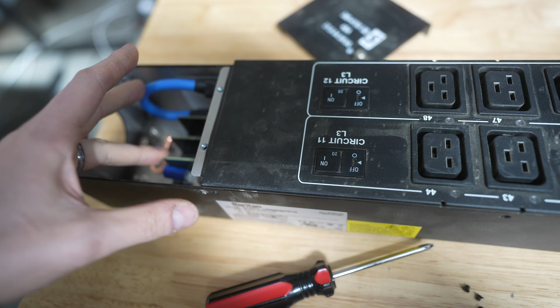35,000. Now, how many can we run on this PDU? So we know that the maximum load is 35,000. We're going to be a little bit under that. We checked the maximum load on 6 gauge, and that checks out fine, 35,000 or more. So we know that the copper 6 gauge wire coming out of this PDU is not the problem. The problem is just going to be the PDU, so you have to make sure that we're not overloading the PDU.